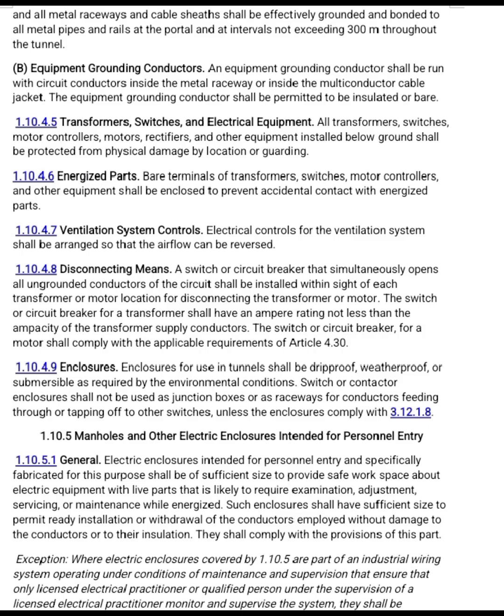The switch or circuit breaker for a transformer shall have an ampere rating not less than the ampacity of the transformer supply conductors. The switch or circuit breaker for a motor shall comply with the applicable requirements of Article 4.30. 1.10.4.9 Enclosures. Enclosures for use in tunnels shall be drip-proof, weatherproof, or submersible as required by the environmental conditions. Switch or contactor enclosures shall not be used as junction boxes or as raceways for conductors feeding through or tapping off to other switches, unless the enclosures comply with 3.12.1.8. 1.10.5 Manholes and other electrical enclosures intended for personnel entry.